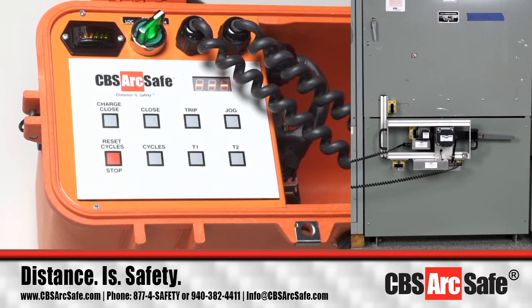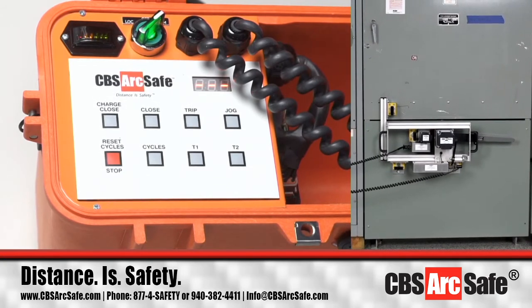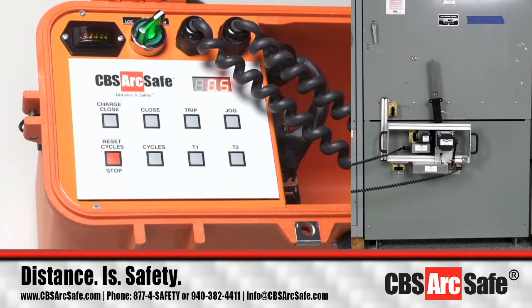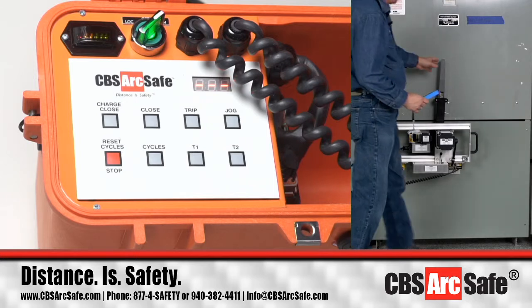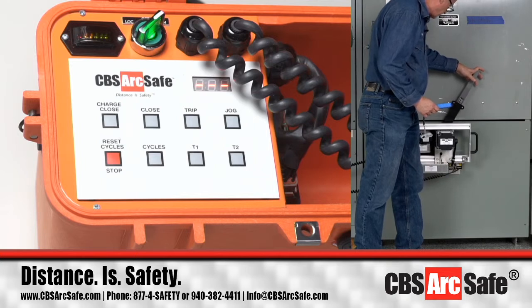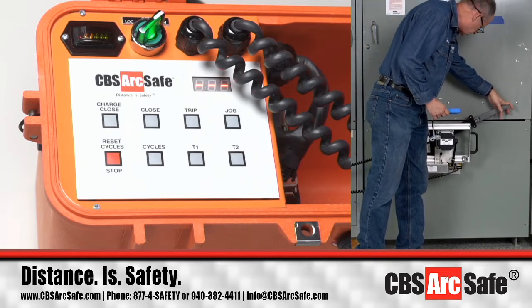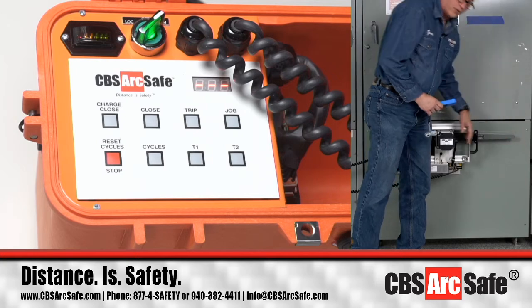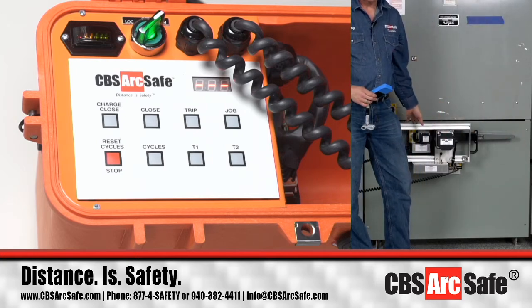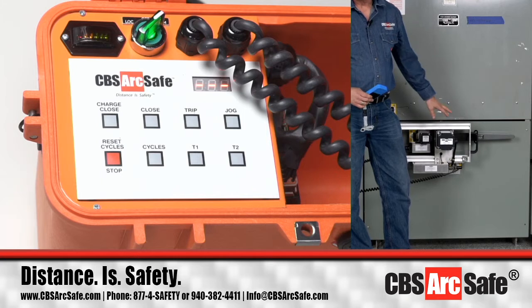For charge close now, we'll just push our charge close button once. You hear the switch close right there. Then for the trip, we'll hold it down, and the handle will actually release. I can either push it back down the rest of the way after it's accomplished the trip, or if I want, I can use the trip actuator by itself and do that without this on there.